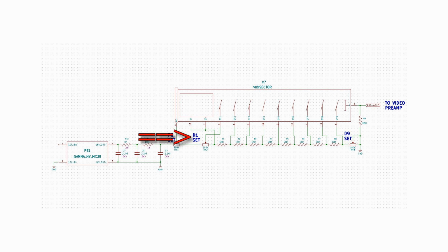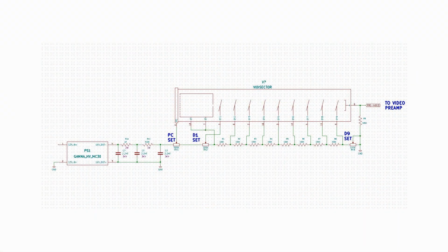Back to the schematic. The second resistor in the chain is another variable resistor which adjusts the voltage of the first dynode. The 9 diagonal lines on the left of the symbol represent the dynodes inside the electron multiplier tube. As they proceed from left to right, they become more positive by approximately 100 volts, though this can change depending on the pot settings. The final pot sets the entire current of the chain and can move the voltage on the dynodes like an accordion, maybe 80 to 110 volts apart, setting the gain of the dynode chain.